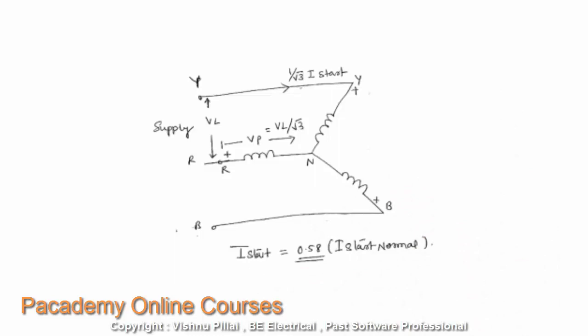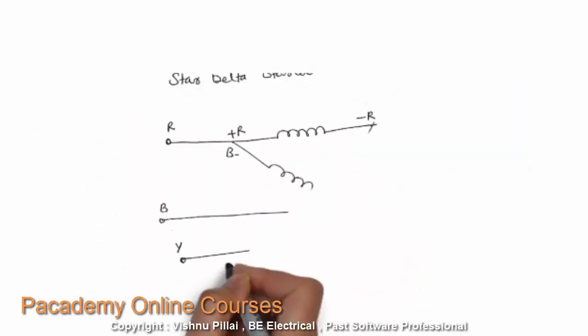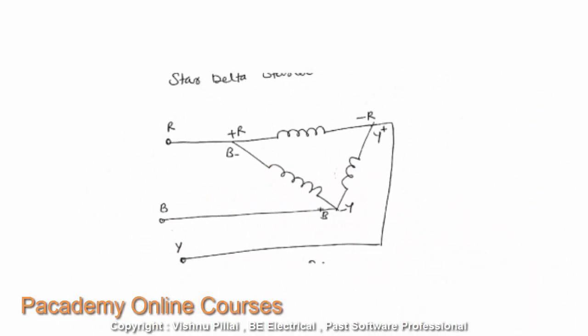Another starting arrangement is the star-delta starter. As shown here, the stator circuit is connected to the supply in star while starting. In a star connection, the phase-to-neutral voltage will be the line voltage divided by root 3, so it will be reduced by a factor of 0.58. The starting current, which is directly proportional to the supply voltage (V divided by impedance), will also be reduced by a factor of 0.58. While the motor is running, it is reconnected in delta, so the full line voltage applies across the phases, as you can see in the diagram. Only at the time of starting is there a reduction in starting current.